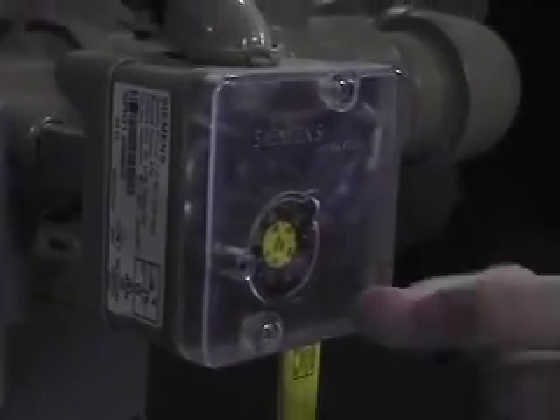But this is the reset button, so if you get that call, you can't get the boiler to start, fan won't start, well, gas might be tripped. So check here, this little black button will be poking out, you just push it back in and you'll hear it click. If it tripped, don't just say, okay, everything's fine, and walk away. It tripped for a reason. You've got to go back and troubleshoot the system. Why is it tripping? Why did my gas pressure drop below, or why did my gas pressure jump higher than it needed to be?